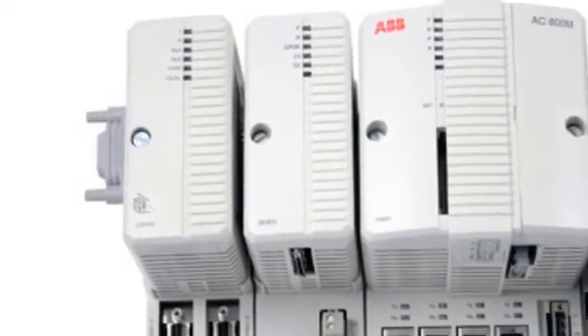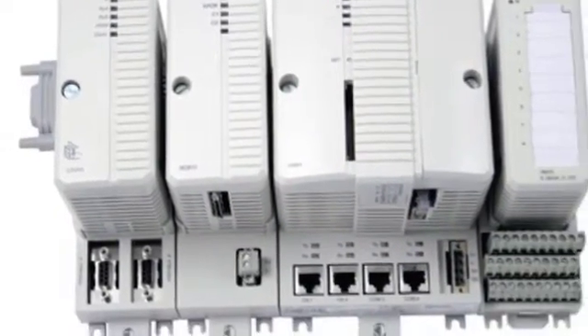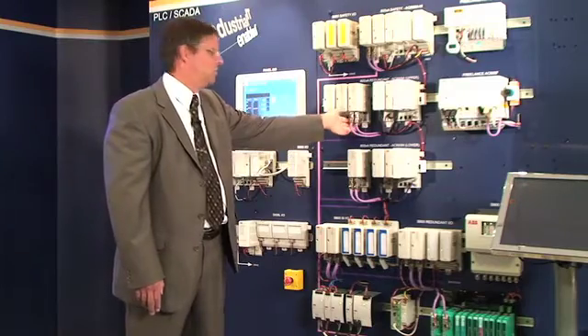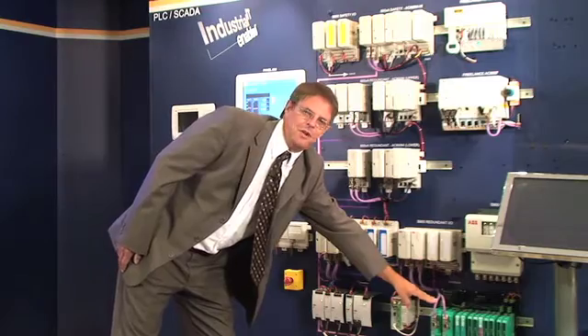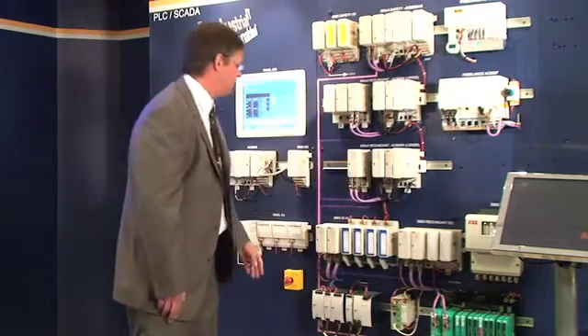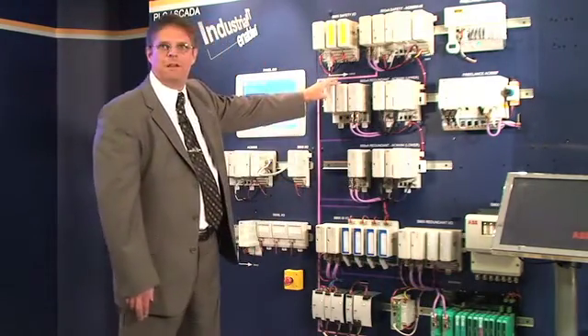Now, on the left-hand side of the controller, you always have the communications. Here we have Profibus in a dual format, so that's Profibus DP, coming out to a DP to PA converter and then going out into your field instrumentation.